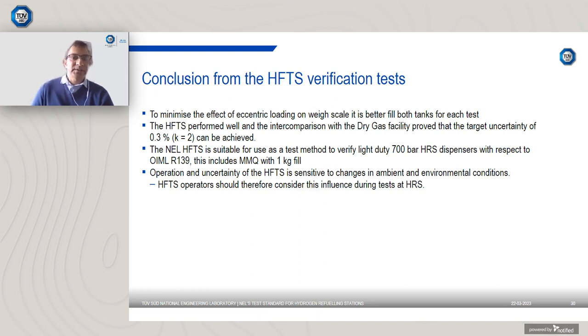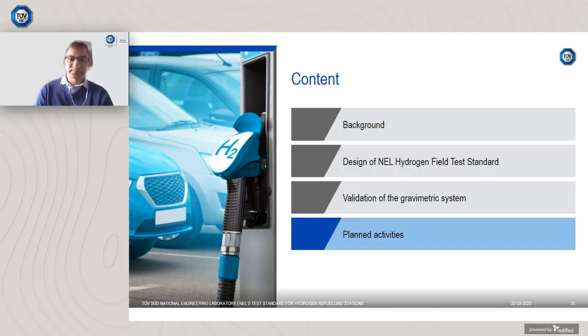And because of this, we could say that the test rig is suitable for use as a test method to verify hydrogen refueling station dispensers with respect to the OIML R139 standard, and this includes the minimum measured quantity fill, which is a 1 kilogram fill. What we also found is that the test rig is quite sensitive to changes in ambient or environmental conditions, and therefore this is something that operators need to take into account when they use this test rig at hydrogen refueling stations.